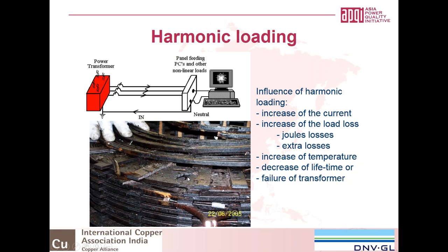There was not sufficient cooling, and later on we found out that the specification of the transformer didn't mention that this transformer was going to be used in a harmonic rich environment. So that's definitely something to consider in case you want to buy a transformer, and later on I will show you what will happen in case you don't. Make sure that in the specification you also mention to the manufacturer that it will be used in a harmonic environment, because he needs that for the cooling, and also to make sure that he makes the right choices to reduce the extra losses.